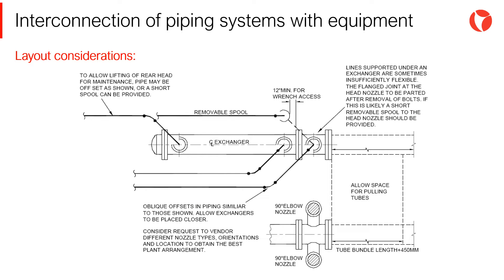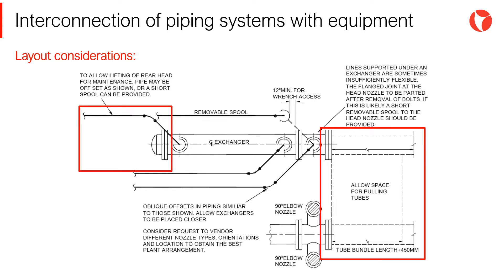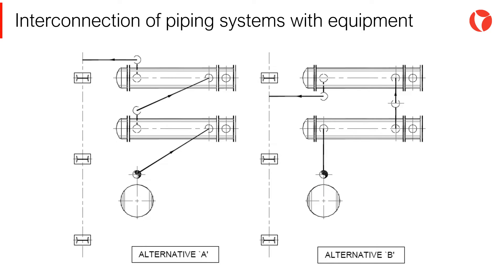It is critical and essential that the space in front of the exchanger is free to facilitate extraction of the tube bundle. Likewise, the pipes reaching the rear of the equipment must leave free space for the rear head to be hoisted. As shown on the screen, there is no single acceptable configuration for the interconnection of this type of equipment. The designer must follow the operation and maintenance requirements and at the same time come up with the most economical designs possible.